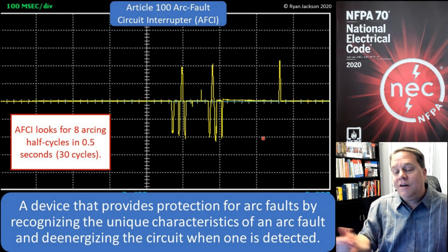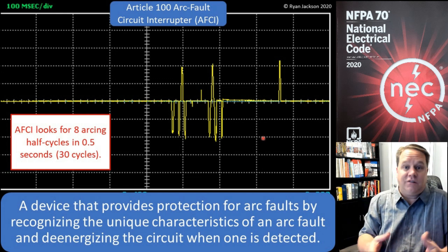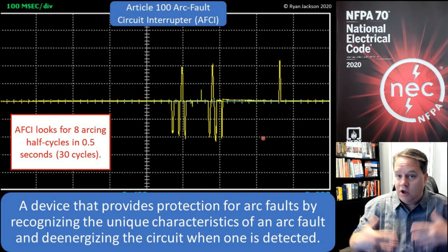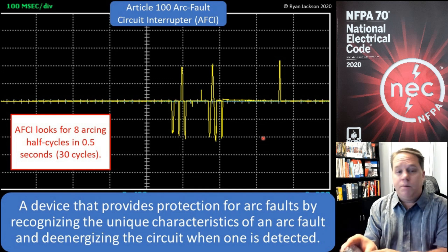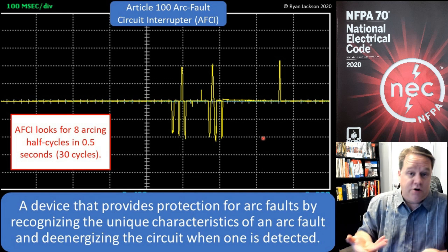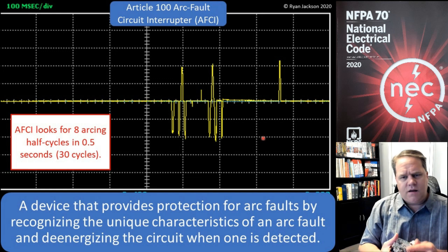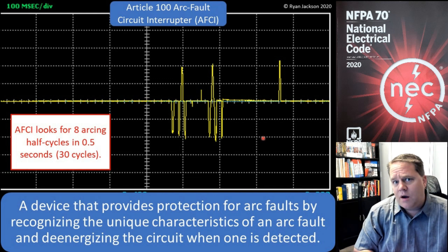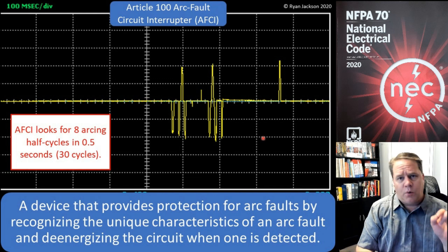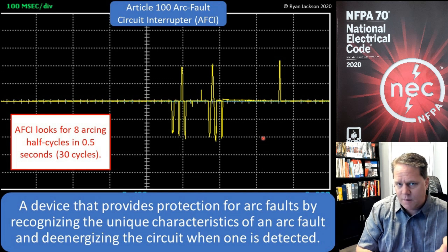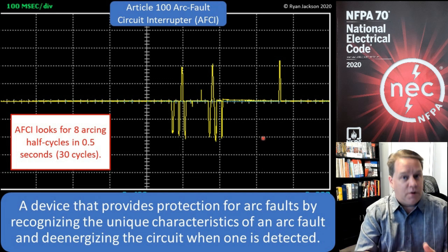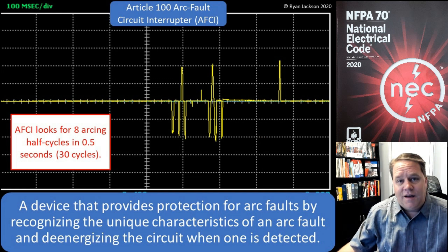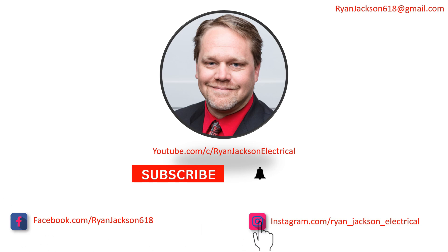GFPE is a great feature in a circuit breaker, but let's talk dollars and cents: if each component costs a dollar and you sell 250,000 breakers, that's a quarter million dollars. You can see why manufacturers don't put anything in there that doesn't have to be there, especially since people already complain about the price of AFCIs. That is an AFCI. NEC 210.12 is where you see the code rules for AFCI protection, and also 406.4(D) for replacement of receptacles. Today we're just covering the definitions, and that's the definition of an AFCI.